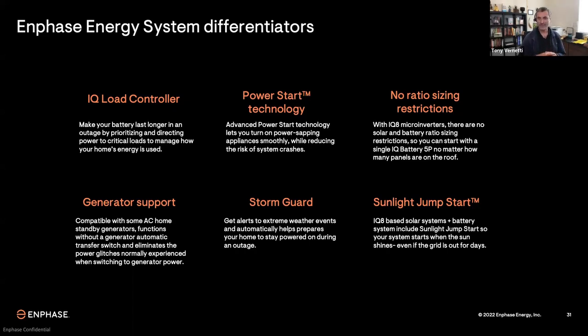We also offer Power Start technology. This is by default how the battery works. When I was talking about the locked rotor amps startup capability of our system, this is what it's all about. So it's not just the peak power of the microinverter. Power Start actually is made possible by the super fast microprocessors in our system. If there's a load that's demanding a very high amount of power, it is able to react. All the microinverters in the system can react almost like a choir of singers and make a quick adjustment to the voltage of that microgrid. It lowers the voltage very quickly and temporarily in order to allow that appliance to start, and then it'll immediately ramp that voltage back up. And that basically gives it an extra effective boost of power to start motor-driven appliances.